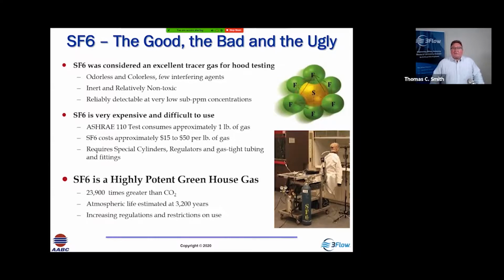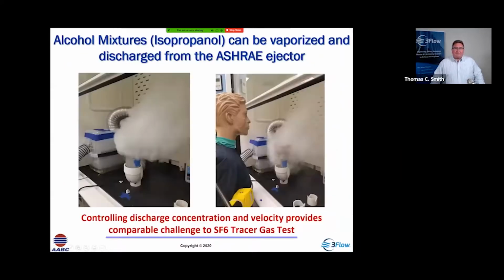It also requires some very specialized equipment from detectors. You've got to have gas-tight, leak-tight fittings. You've got to have a special regulator and stainless steel tubing and so forth in order to properly conduct tests. Very complicated test. What we found out during the ASHRAE project is that we could generate other materials. And in fact, we could use a material as simple as isopropyl alcohol. We could nebulize it and generate a plume that could simulate the SF6, and then we could use that as an alternative to SF6 testing.